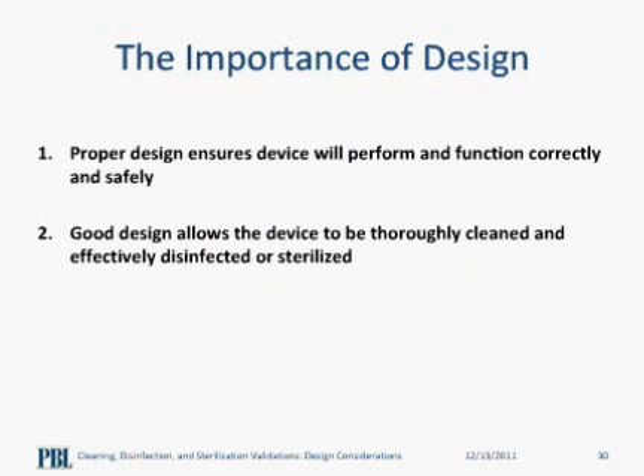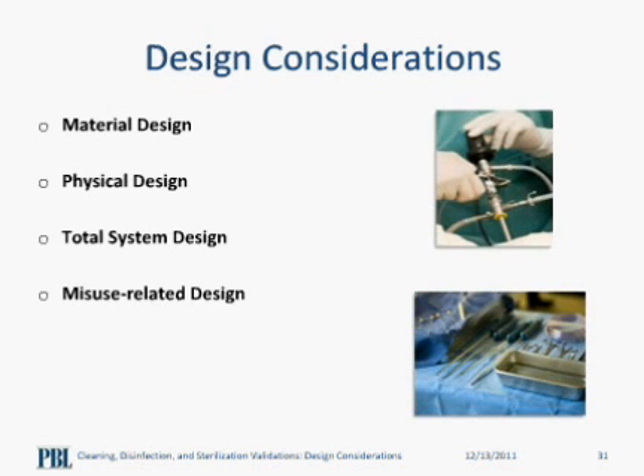It is now required to have validated reprocessing instructions before a product can be labeled as reusable. We all know that a well-designed device can be thoroughly cleaned and effectively disinfected or sterilized, whereas a poorly designed device is difficult to clean and more likely to be damaged as compared to a well-designed product. There are 4 design aspects to consider in manufacturing reusable medical devices. We have material design, physical design, total system design, and misuse-related design considerations.